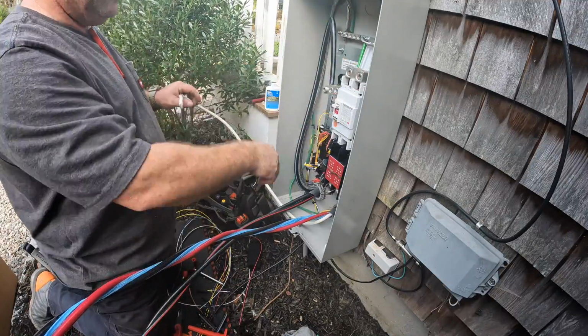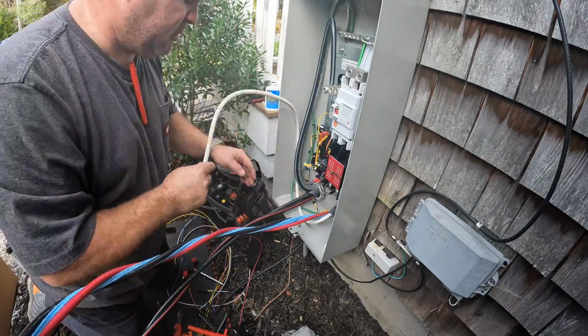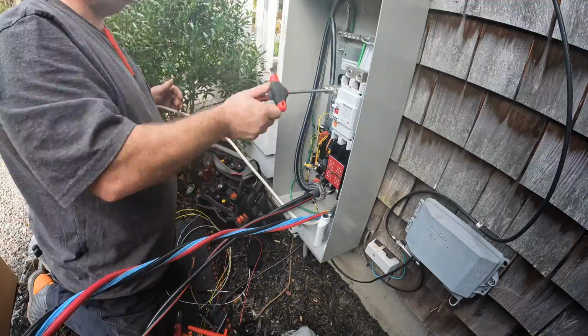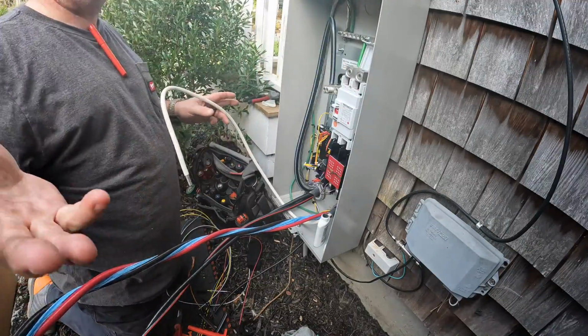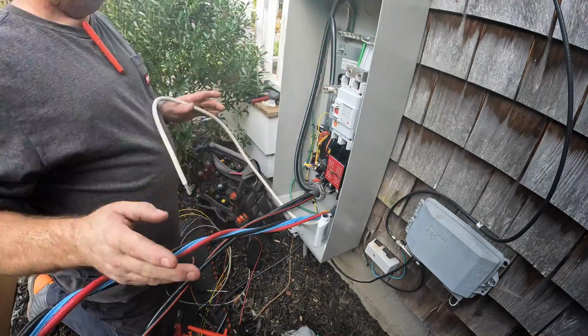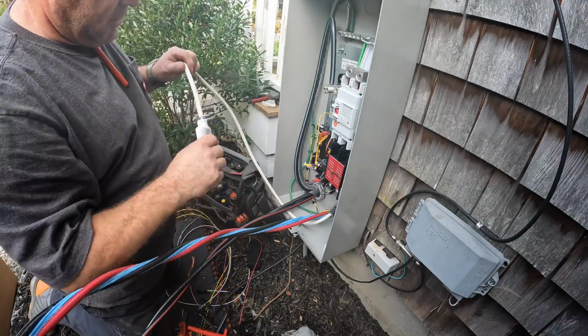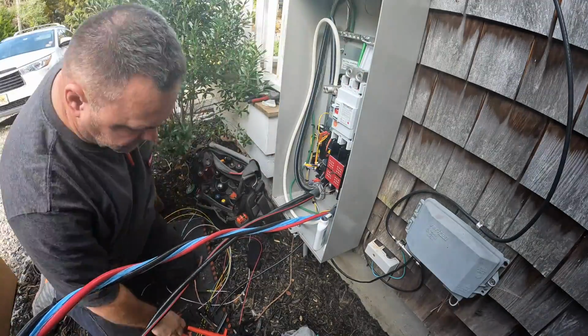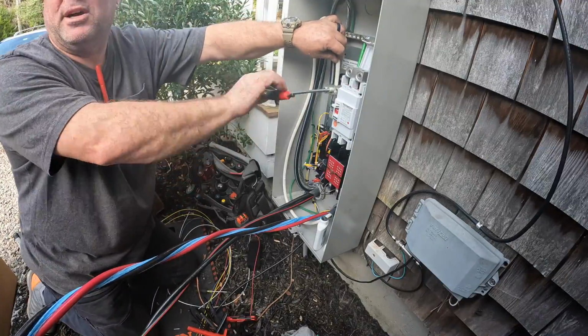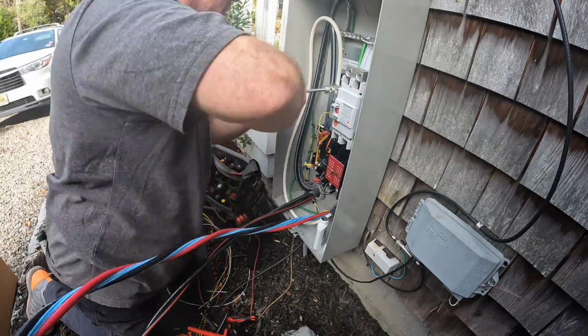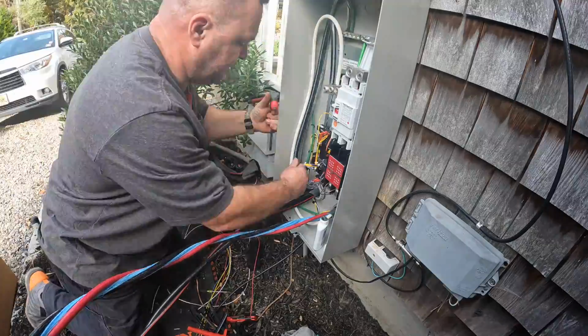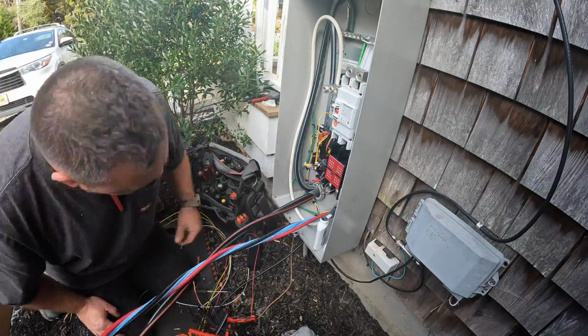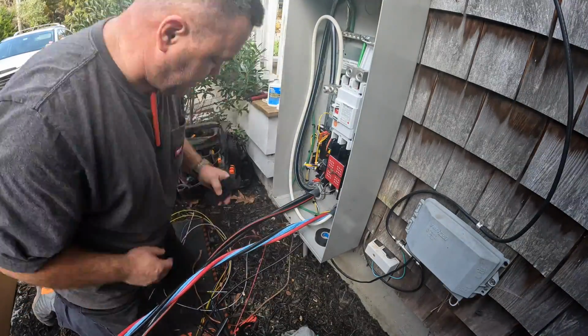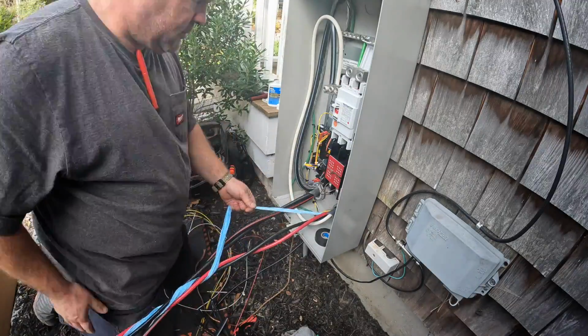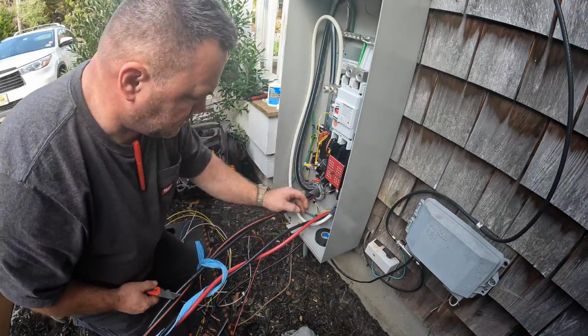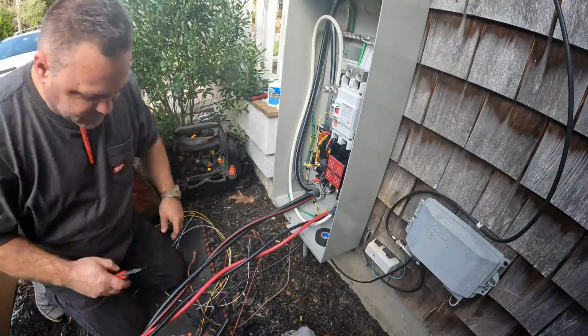Now, when I'm terminating these conductors, what I like to do is terminate all my equipment grounding conductors first, and then all my grounded neutrals second, before finally connecting my generator cable and, of course, the panel. It just makes sense to do that because all these wires, you want to put them in a nice workmanlike manner. If you do these first in this order, the conductors will sit nice and neat inside the transfer switch here, which is what any good tradesman will do.